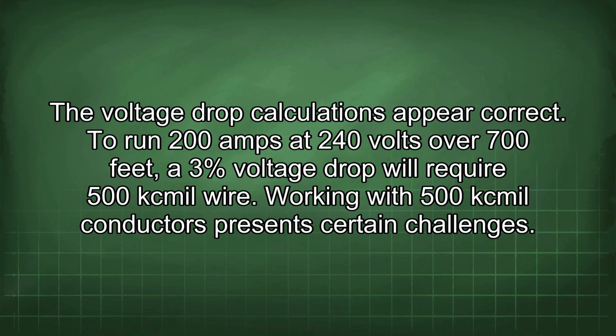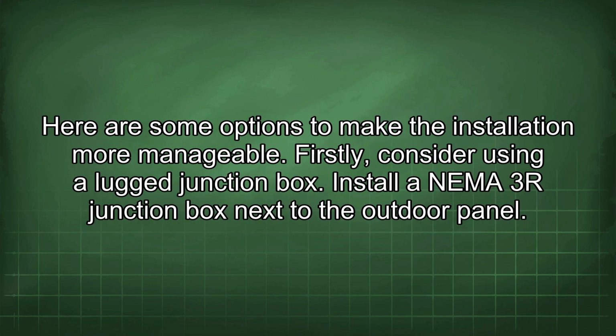Voltage drop calculations appear correct. To run 200 amps at 240 volts over 700 feet, a 3% voltage drop will require a 500 kcmil wire. Working with 500 kcmil conductors presents certain challenges. Here are some options to make the installation more manageable.